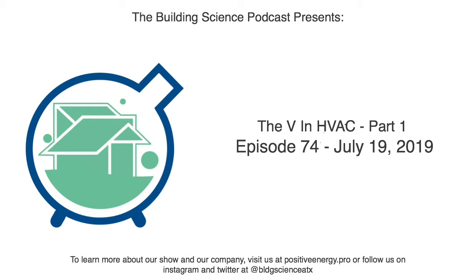And so now, let's say we start out with a 92 degree outdoor air temperature. It goes through the core. It goes from being outdoor air to becoming supply air, and as supply air with the 90% effective recovery, it now becomes 92 minus 18, so it's going to be 74 degrees. You can see why I said it would have quelled that initial fervor: like, no, you can't bring all this ventilation here. It's like, no, what if it's 74 degrees? Yeah. But now, can these things be 90% effective? Let's talk about that in a minute. Okay, lead me to it.